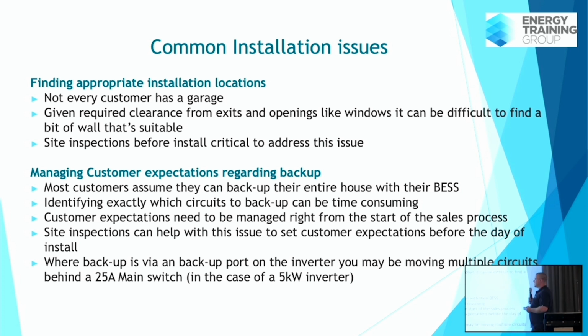Managing customer expectations regarding backup is really important. When you do a handover at the end of an installation, you need to make sure you communicate to the customer how the backup works. They need to understand they can't just turn on every single thing in their house when they're in backup mode. They're used to having the grid, and they think backup is just like the grid, but it's not - it's a current limited source. There's only so much they can run on backup.